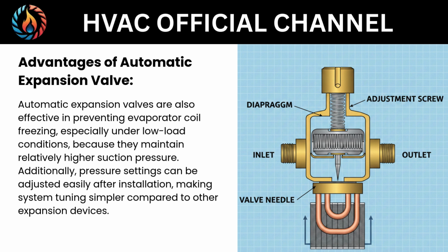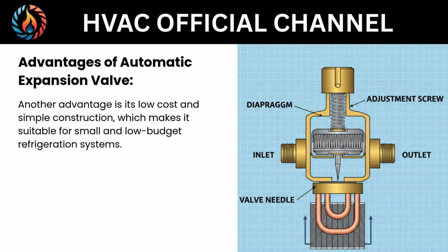Automatic expansion valves are also effective in preventing evaporator coil freezing, especially under low load conditions, because they maintain relatively higher suction pressure. Additionally, pressure settings can be adjusted easily after installation, making system tuning simpler compared to other expansion devices. Another advantage is its low cost and simple construction, which makes it suitable for small and low-budget refrigeration systems.